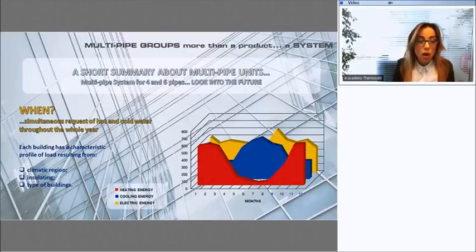Before starting with the presentation of the new range, we will make a very short summary about the multi-pipe unit. When to use a multi-pipe unit? Of course, the multi-pipe unit is suitable and needed when there is a simultaneous request of hot and cold water during the whole year. This depends on the building load profile, which results from the climatic region, the building insulation, and the type of building.